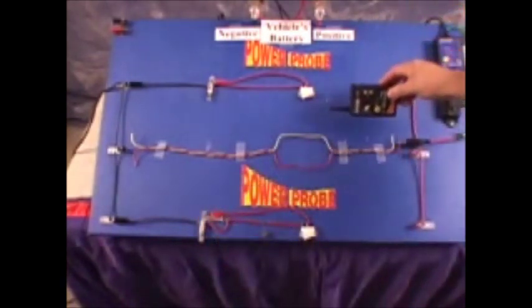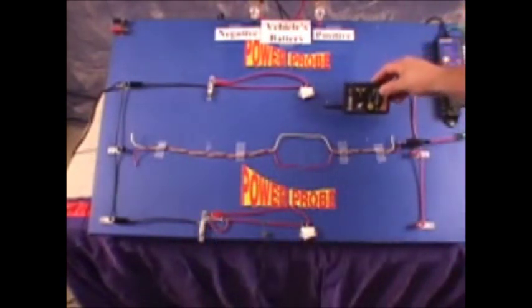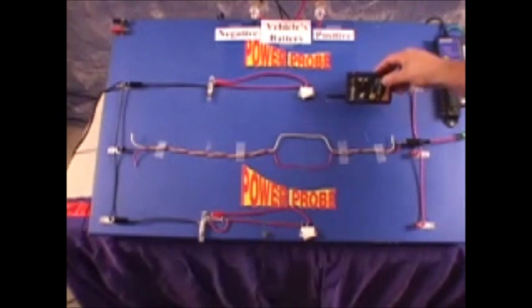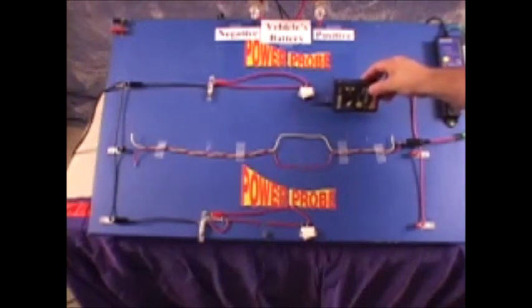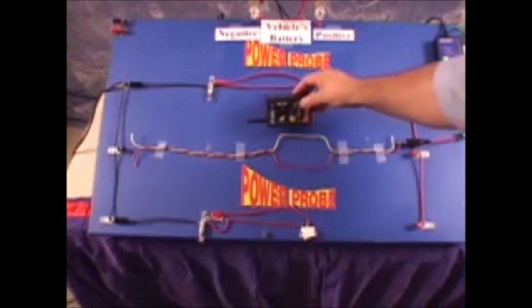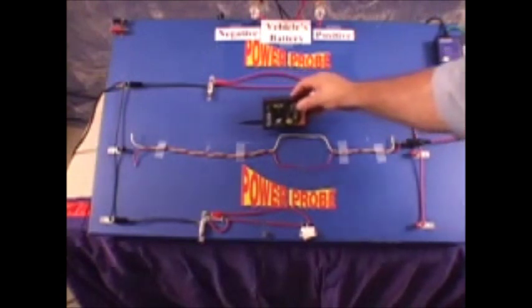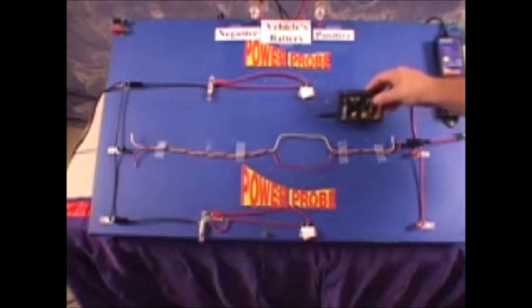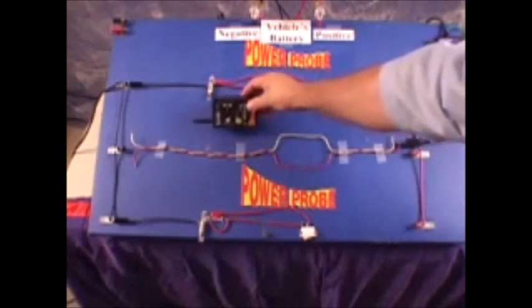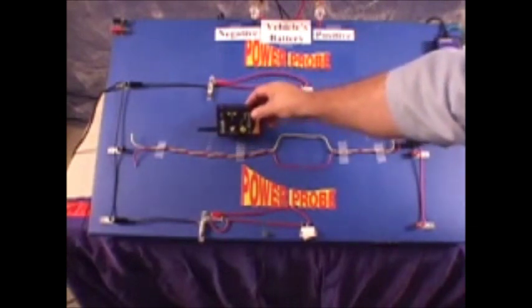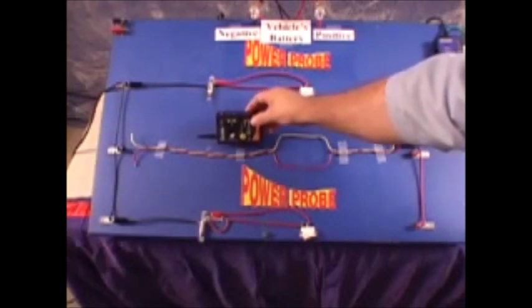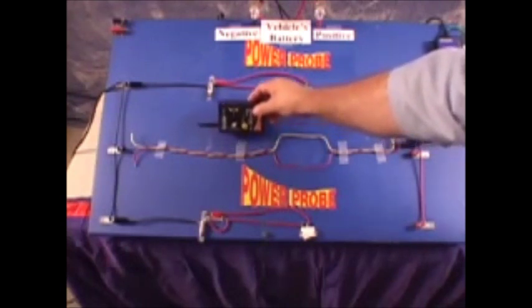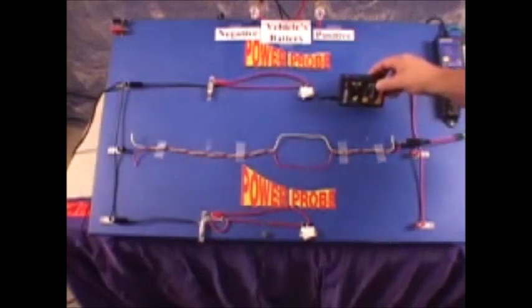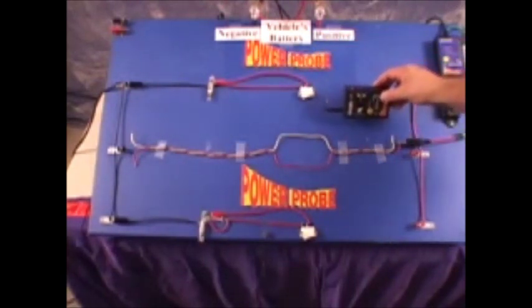Remember to hold the distance between the receiver and the circuit as you trace it out. Here, the strong signal is being detected about 4 inches away. As you can see, by holding it about 4 inches away as you trace the circuit, the signal stops right when you pass over the cut in the wire. I like to gauge the reception distance often so I know we're on the right circuit. So if I come across another wire that requires me to get closer than 4 inches before the signal detection, I know instantly that it's a weak signal and I need to avoid following this wire. We need to stay on the wire that detects the signal about 4 inches away.